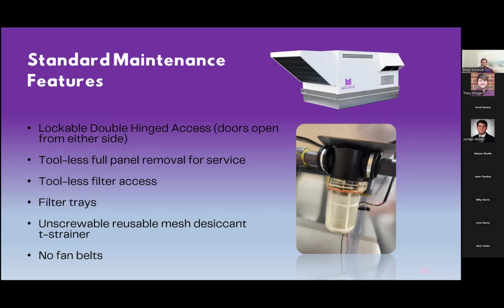But the channels in the pad go down at an angle like this. So as that liquid desiccant is flowing down, it's kind of filtering to the outside of the pad. That allows those contaminants to fall down into the tank at the bottom of the pad itself. And then these T strainers, before each pump, are going to filter any particles out. What we recommend is, when you change your filters, fingers crossed, every 3 months, have the maintenance staff check these T strainers as well. If there are particles in the T strainer, you just unscrew it, toss the contaminants out, rinse it with a bottle of water, and stick the T strainer back on there.